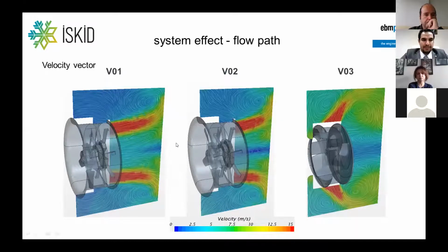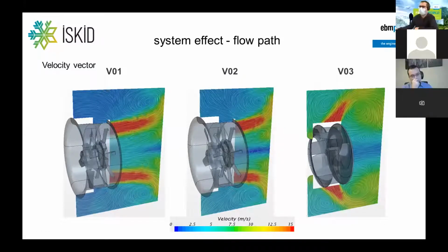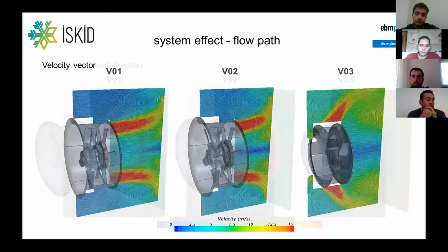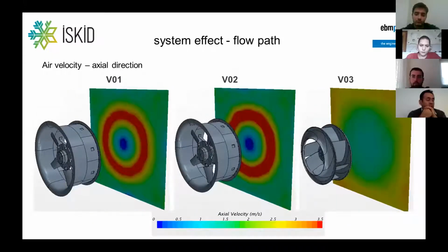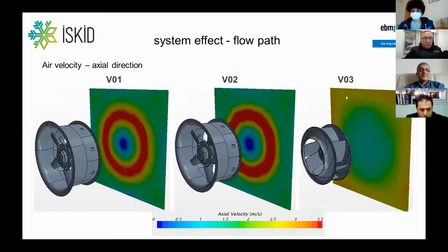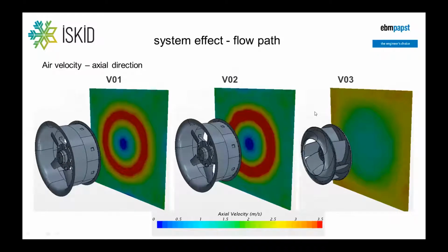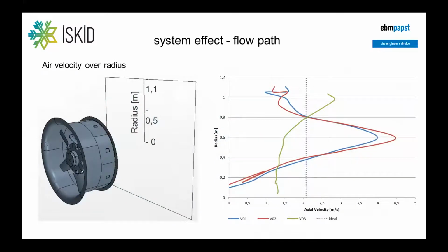distributed airflow. So you see the velocity vectors of the airstream, and you see the red one has quite high speed, and you see here the mixing, the distribution downstream of a centrifugal is better. So if there's a coil downstream of the fan, this coil or filter will have a better effect. So this is another way to express that. And you see here as well on the right, the centrifugal fan, the air velocity through a coil is well distributed. Another way to express that one.